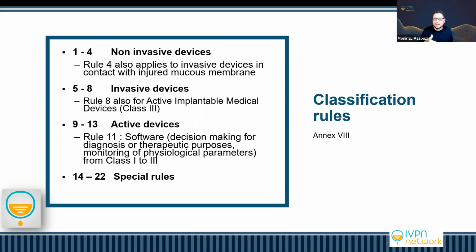EU MDD didn't have these rules, and they were added with EU MDR. If you have nanomaterials within your products, then it's Rule 19. If you have invasive devices with respect to body orifice that administer medicinal products, then it's Rule 20.